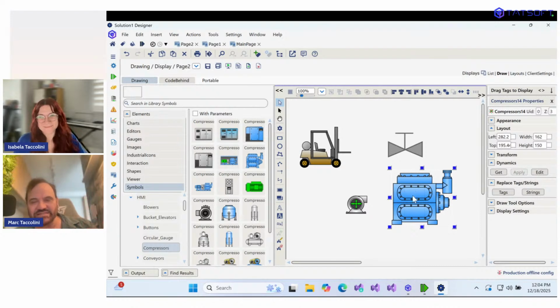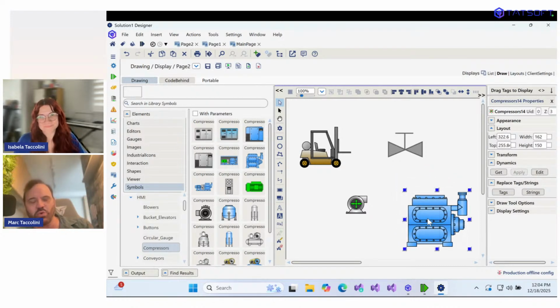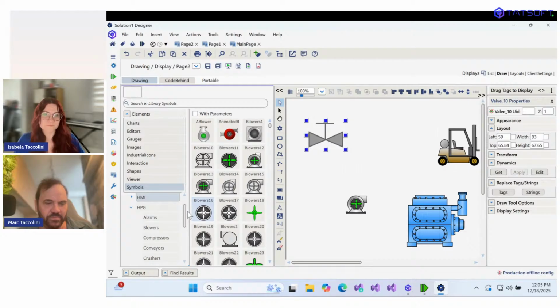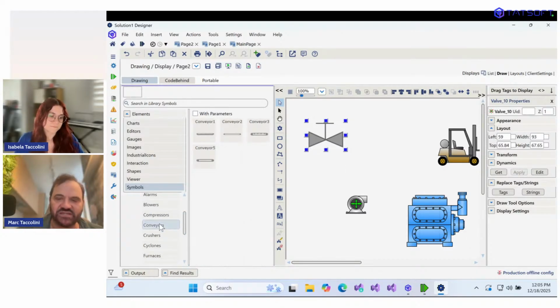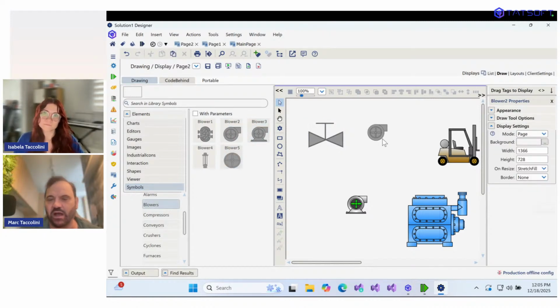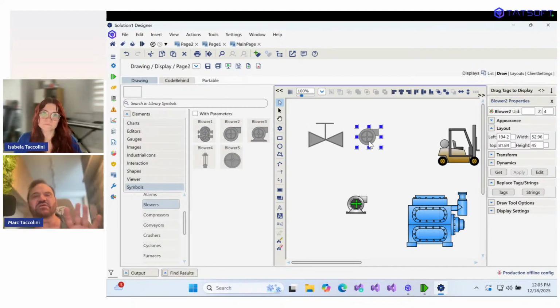But there is also a very strong school, especially in the process industry or in chemical or pharma, where you have very critical processes and more training for the operators. They are going to another strategy, which is to do displays that are much simpler, where the elements on the display don't try to mimic exactly the equipment in the field, but use very simple standard colors.